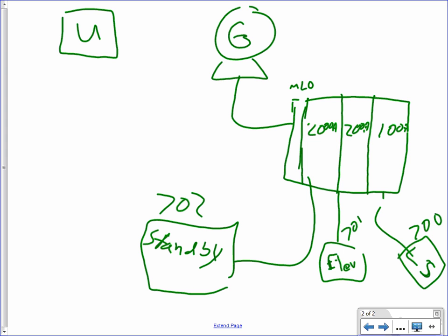Now, if you had more emergency loads over here, you could keep putting breakers in here. If we had an elevator, now we have a fire pump that's 800 amps. As long as they're the same article, you can put multiple breakers in sections. And we do have the ability to put steel barriers between sections. As long as they're barriered off, you can do this in one switchboard.